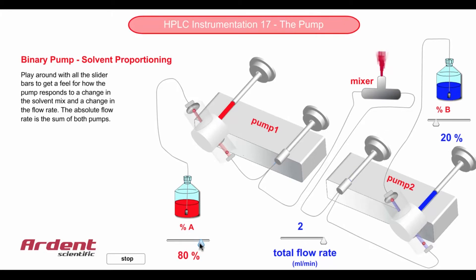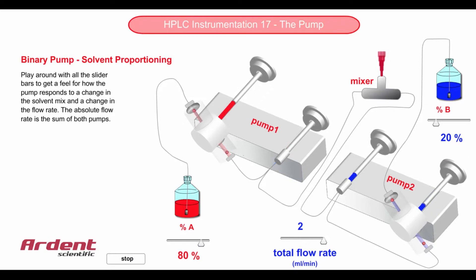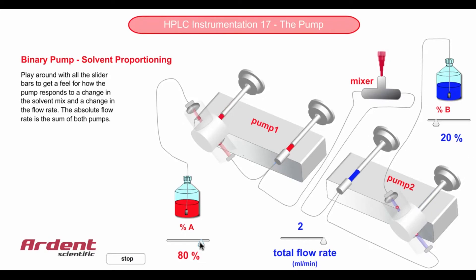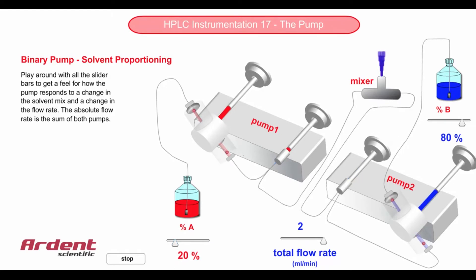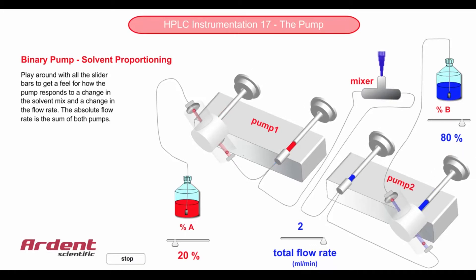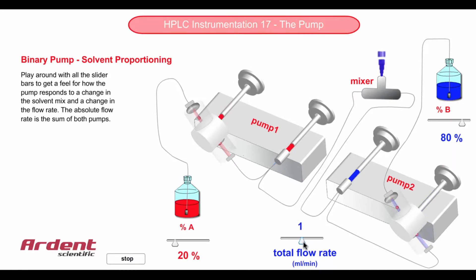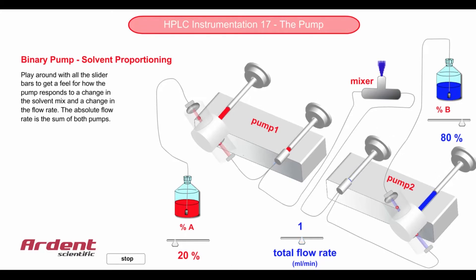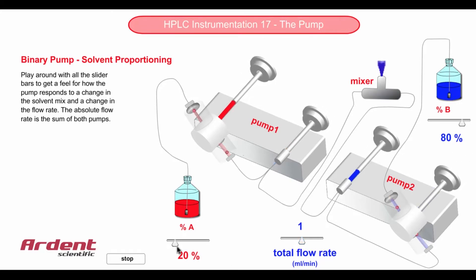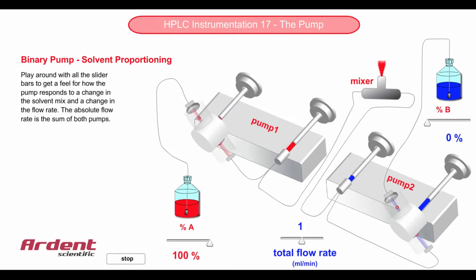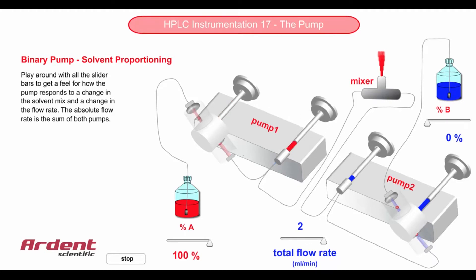If we increase the ratio of solvent A to 80%, we can notice that pump one speed is much higher than pump two to deliver that ratio. In the reverse situation, pump two speed is much higher than pump one to deliver the new ratio. If we need 100% of solvent A, pump one will deliver solvent A while pump two will stop altogether, delivering 100% solvent A.